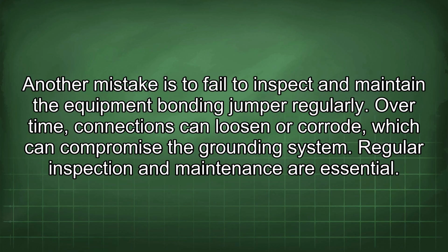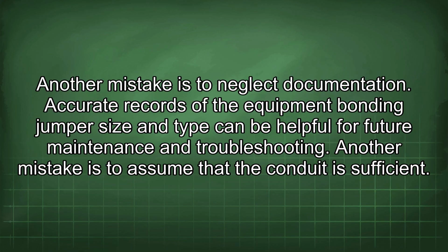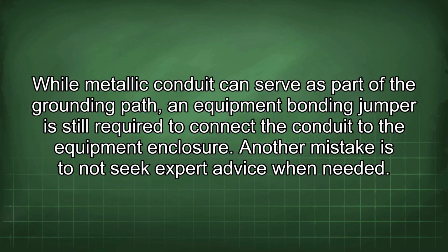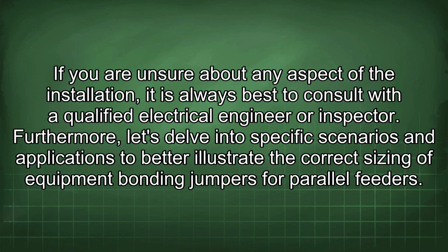Another mistake is to fail to inspect and maintain the equipment bonding jumper regularly. Over time, connections can loosen or corrode, which can compromise the grounding system. Regular inspection and maintenance are essential. Another mistake is to neglect documentation. Accurate records of the equipment bonding jumper size and type can be helpful for future maintenance and troubleshooting. Another mistake is to assume that the conduit is sufficient. While metallic conduit can serve as part of the grounding path, an equipment bonding jumper is still required to connect the conduit to the equipment enclosure. Another mistake is to not seek expert advice when needed.